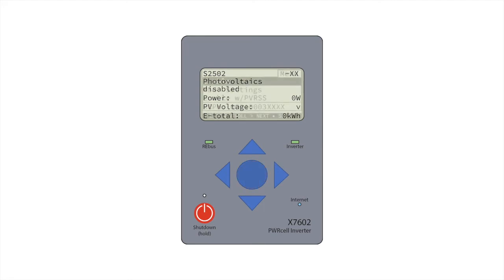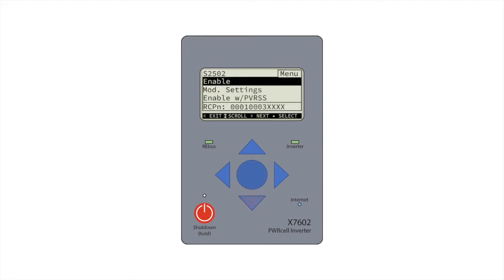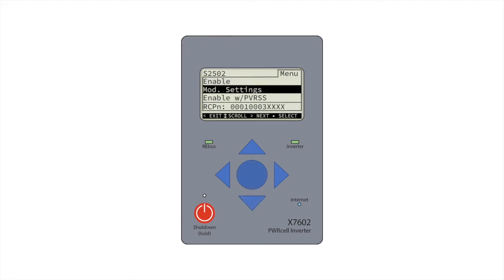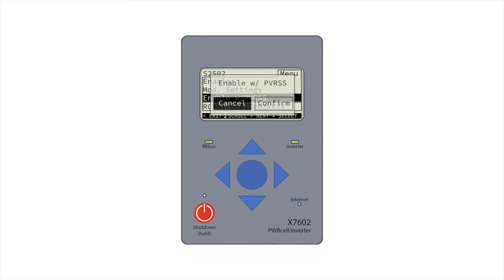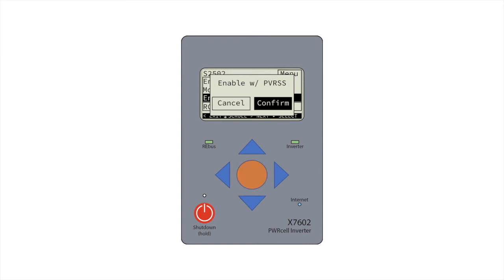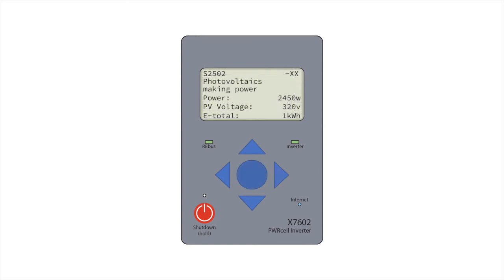The PV-Link tests its substring and counts the SNAP-RS devices. This test can take up to 60 seconds per PV-Link. When complete, it will display making power. If you see a different message, reference the Generac PV-Link and SNAP-RS manuals.